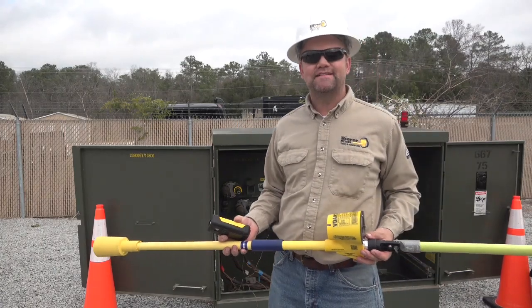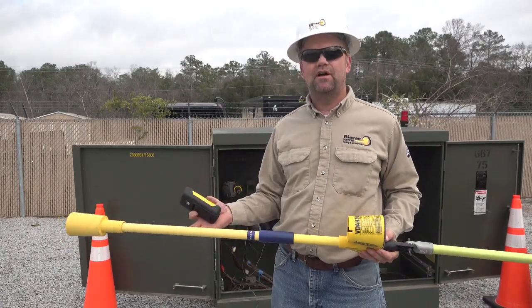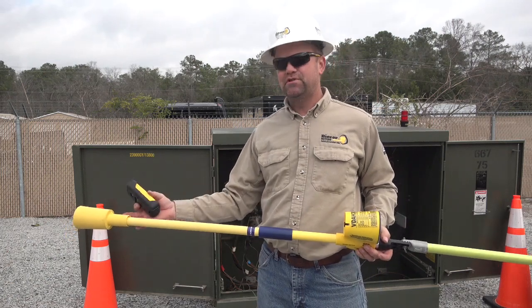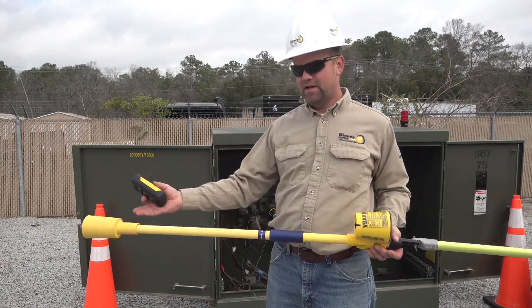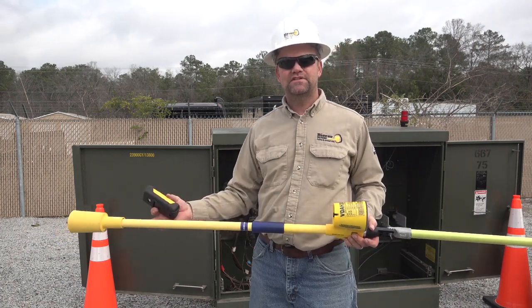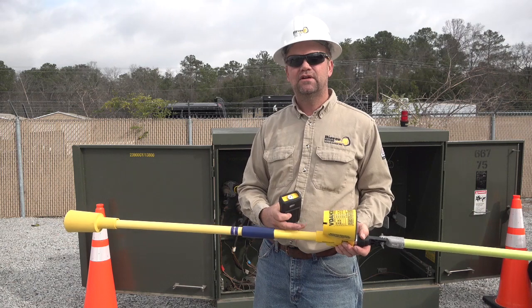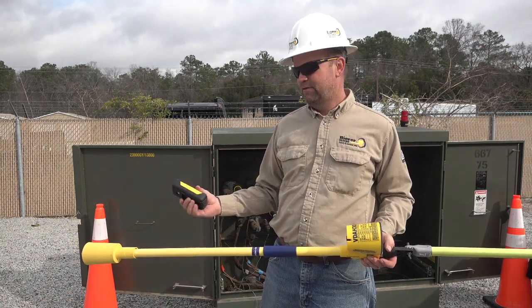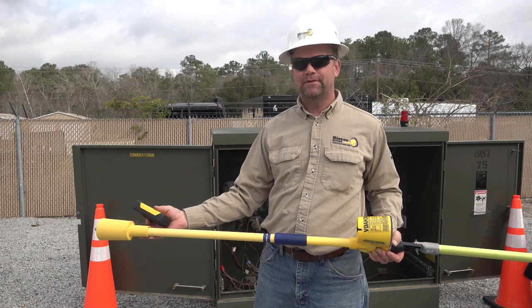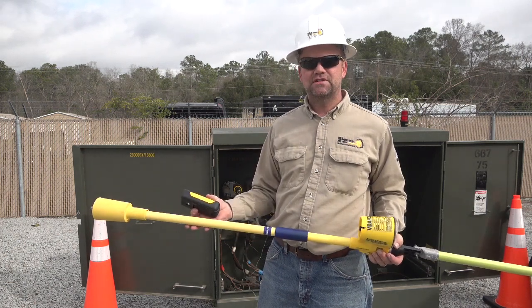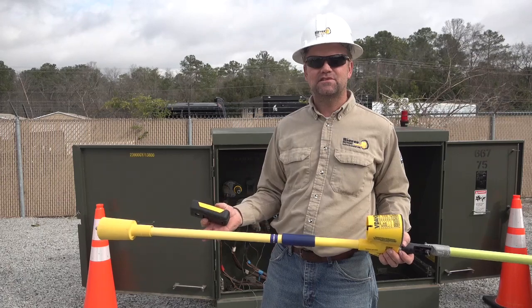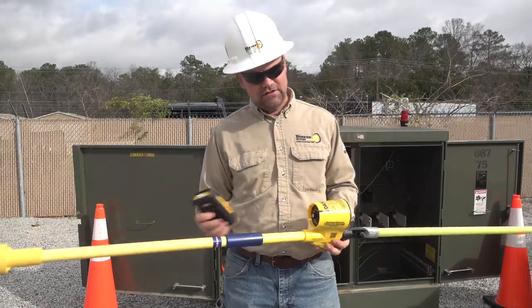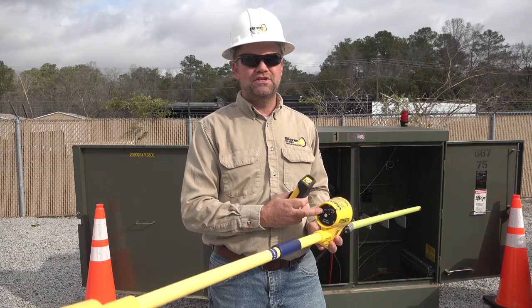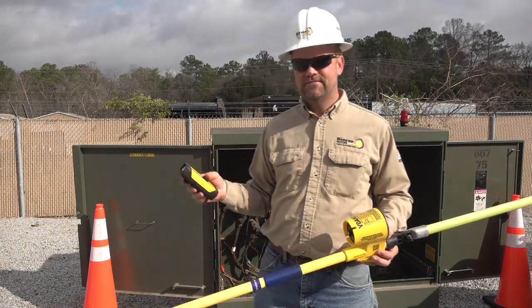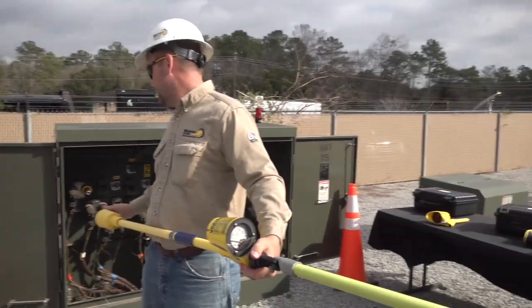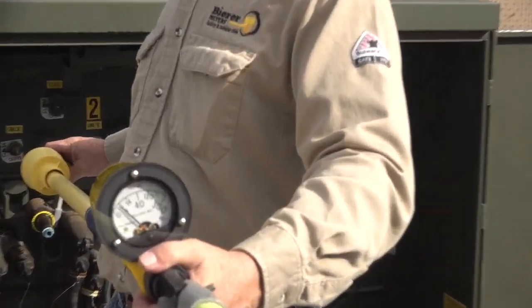I want to check for energized again, but now I've threaded on my 0-ohm extension and I've added my bushing probe adapter. But again, I want to test this whole series of accessories along with my voltage detector before I check for energized. Before, if you remember, I just had my bushing probe adapter, but I did not check my 0-ohm extension. So I want to verify that this accessory is functional. So again, I still have my tool in the first on switch position. I have my handheld power supply. I want to touch the end of the bushing probe adapter and watch the needle deflect.